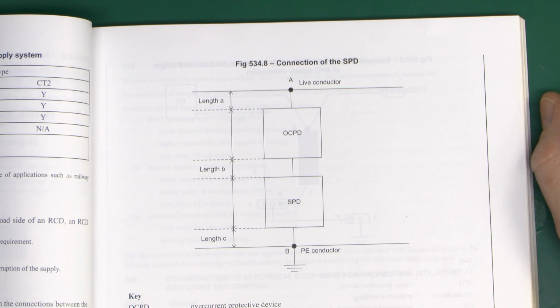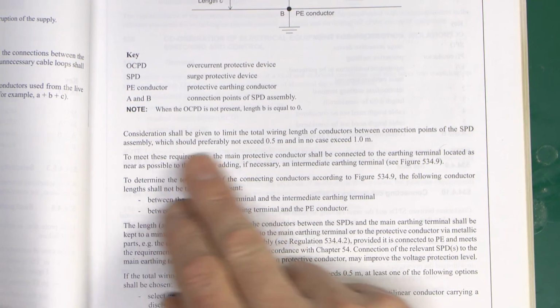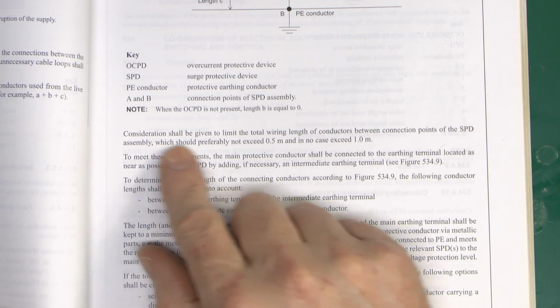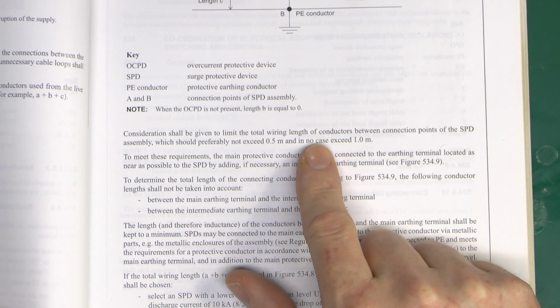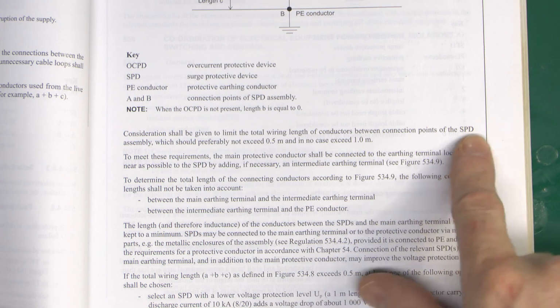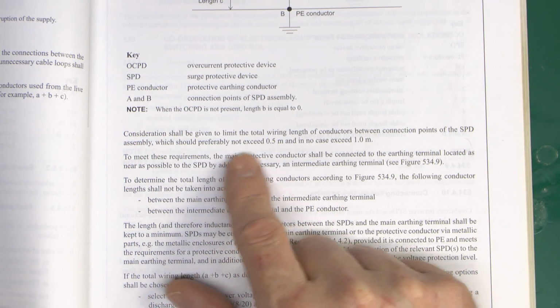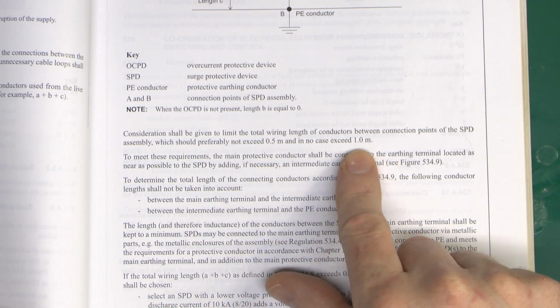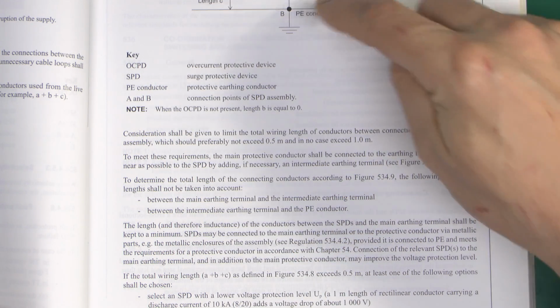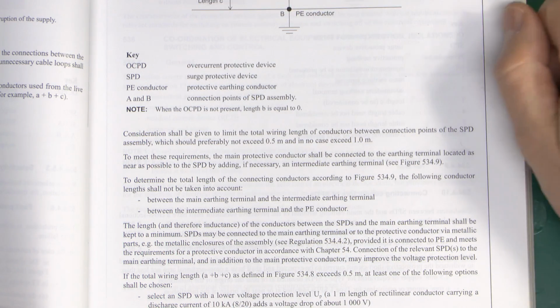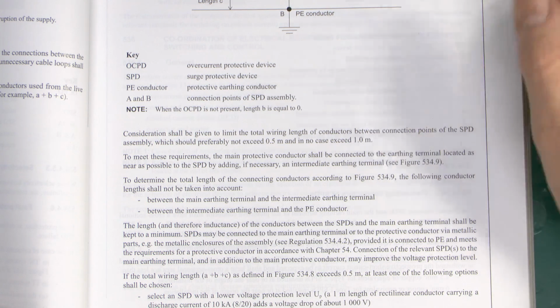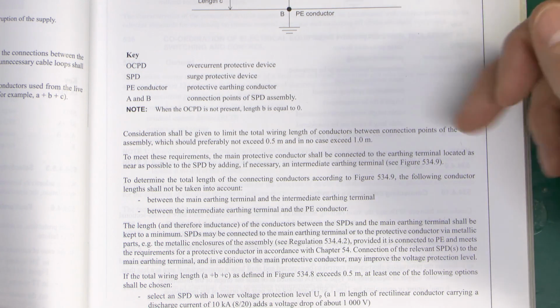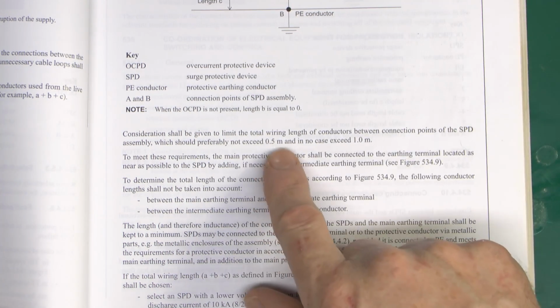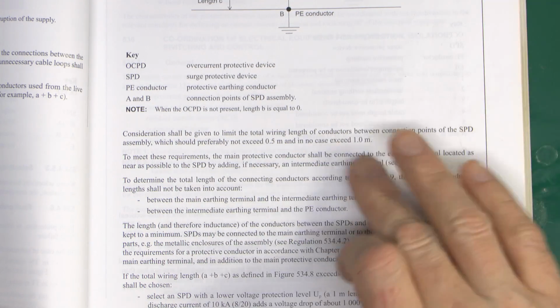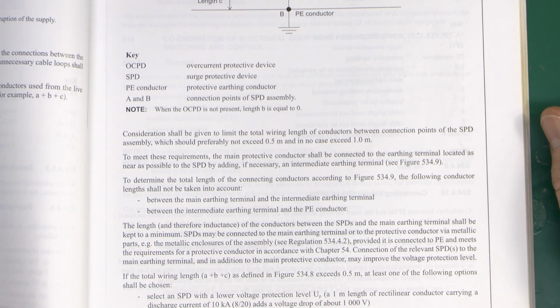So fairly straightforward there. Now the bit here is really the main meat of this, not going to be the whole thing, but consideration should be given to limit the total wiring length of conductors between connection points of the surge protective device assembly, which should preferably not exceed 0.5 metres and in no case exceed 1 metre. So the total of these should not exceed ideally half a metre or 50 centimetres, and your absolute maximum is 1 metre. Now in reality you want to get it as short as actually possible, so even half a metre really is probably going to be your absolute limit. Longer is far, far worse, as we'll see a bit later on.